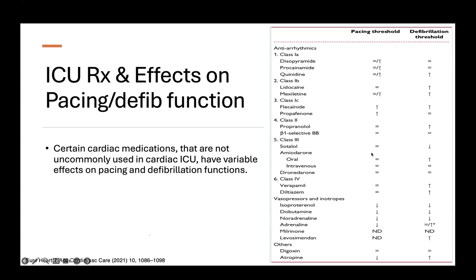And there are other medications that we could see that might have a neutral versus a negative effect on the pacing thresholds. What else to watch for other than the device and medications? Actually, electrolyte disturbances or disturbances in the pH of the blood, either acidosis or alkalosis, might affect it. So here, hyperkalemia actually has variable effects on the pacing thresholds. A mild hyperkalemia increases the excitability and makes the membrane more sensitive. That helps with the pacing thresholds.